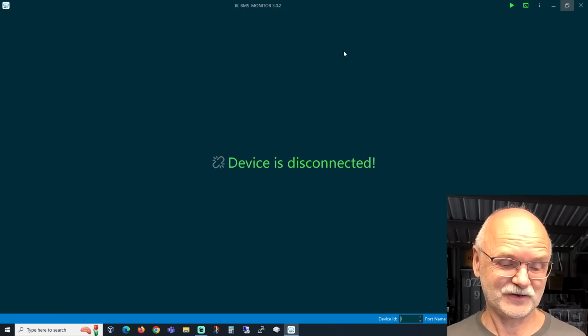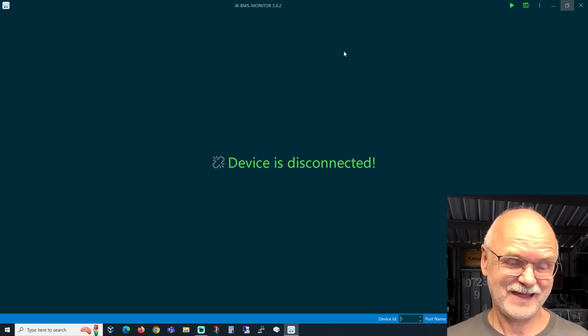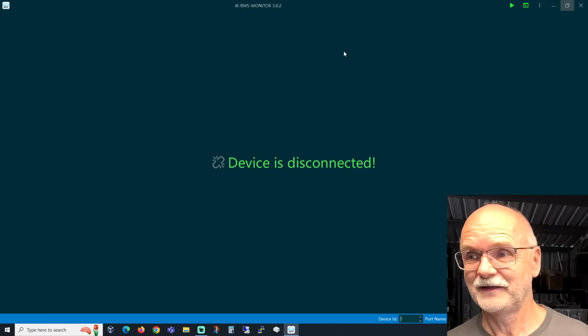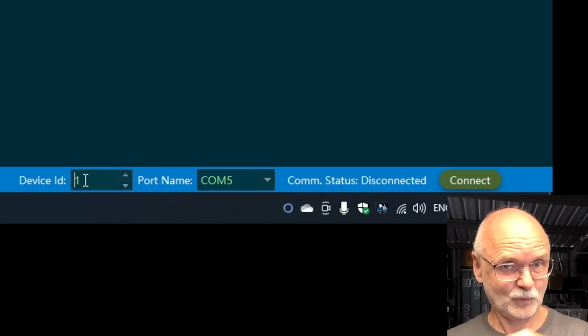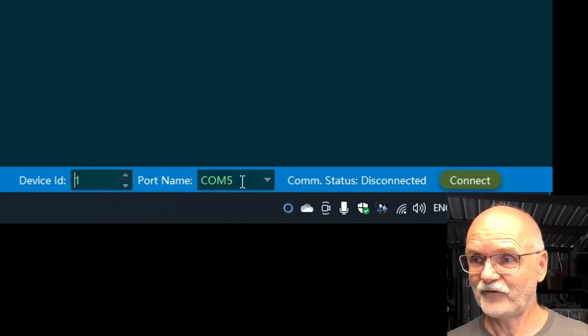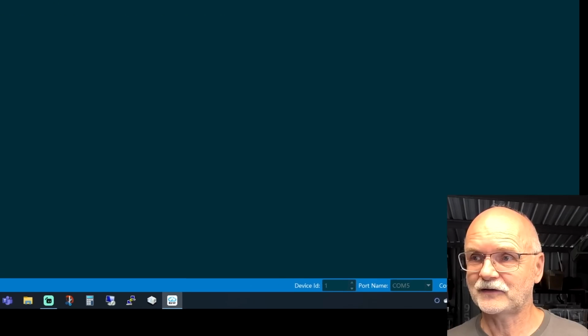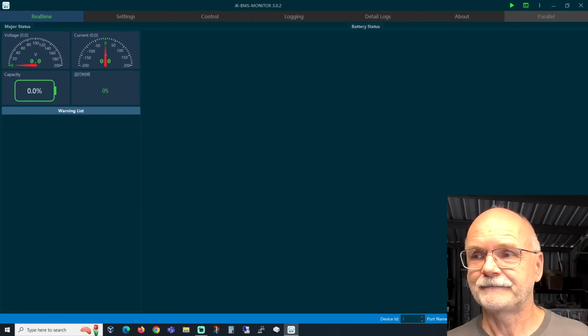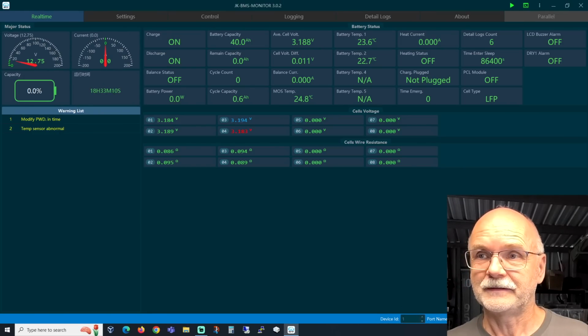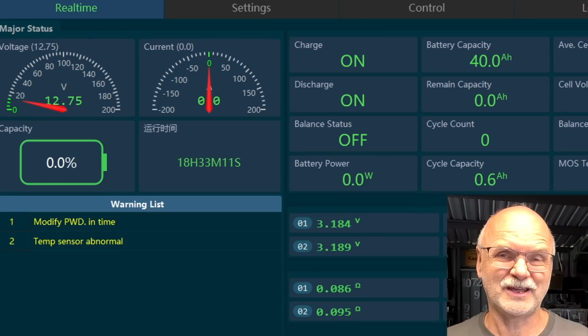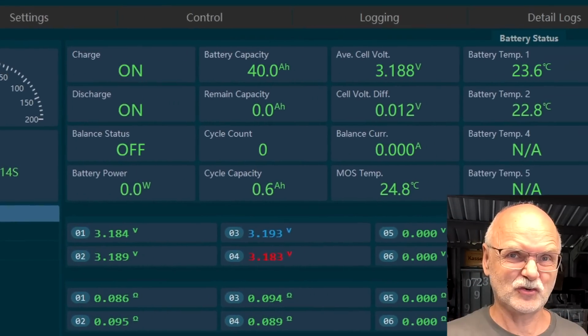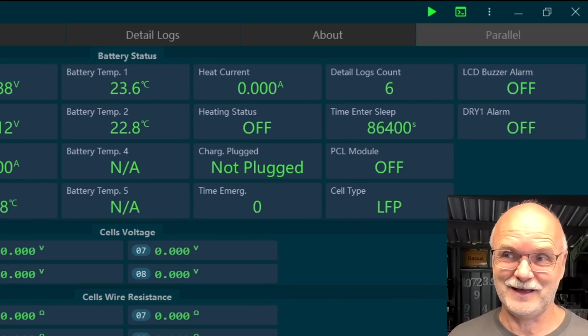Now we can open the JK BMS monitor software, as we have done with the inverter BMS. We set the device address to 1, what we set in the app. COM5 is my internal communication port. Click on connect. And we have full communication from the computer software to the B-series of the BMS now.